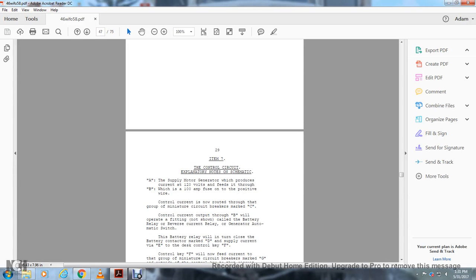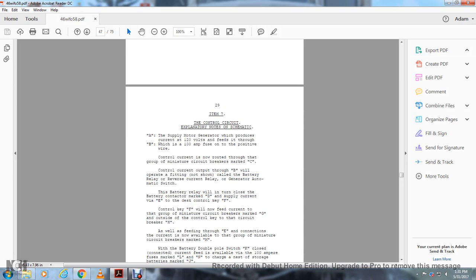Alright, item 7, the control circuit explanatory notes and schematics. A. The supply motor generator, which produces the current of 120 volts, feeds it through B, which is a 100 amp fuse on the positive wire. The control circuit is now routed to the group of miniature circuit breakers marked C. The control current and the output marked output through B will operate the battery relay, the reverse current relay, and the generator automatic switch.